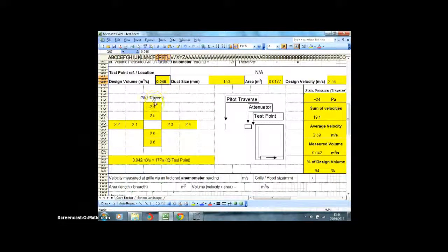As any designer or commissioning engineer would be familiar with, we'll call it a traverse sheet for this exercise, design of 0.045 meters cubed per second, or 45 liters, 150mm duct, so that works out to an area of 0.0177 meters squared, which gives you a design velocity of 2.54 meters a second. Depending on what size of duct you're traversing, you usually do about 12 readings. I did 12 initially, but it came out to just about the same as if I did 8 readings. So 4 readings down and 4 readings across gave me a volume of 42 liters a second, or for continuity, 0.042 meters cubed per second.